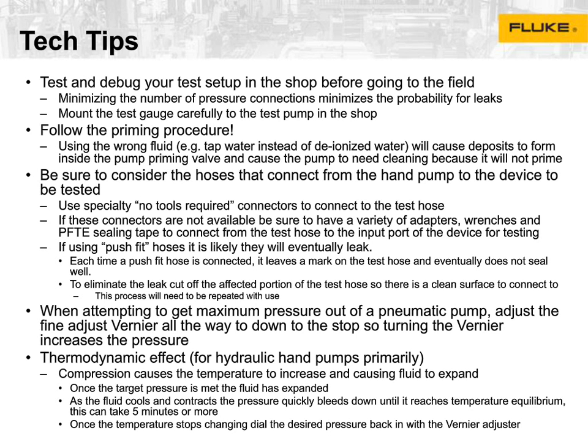As far as fittings and hoses, we find that a lot of the no tools required fittings, like Ralstons, work really, really well. We really like them. And if you don't have those fittings available or your office won't pay for them, make sure you have all of the things you're going to need: adapters, wrenches, sealing tape. And one thing we don't recommend is using push-fit hoses, because they will eventually leak, and you always end up cutting them, and it changes your system every time you do it, and it's going to mess with your repeatability horribly. Just don't do it. Go out and spend the money and either get the adapters and wrenches, or buy the no tools required fittings.